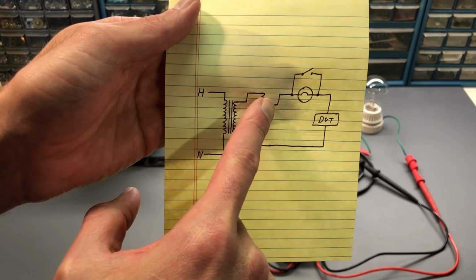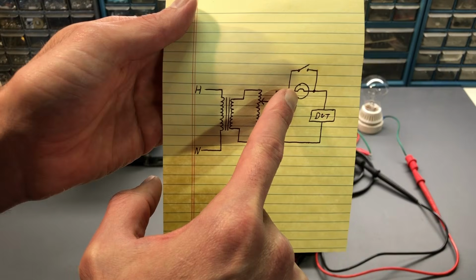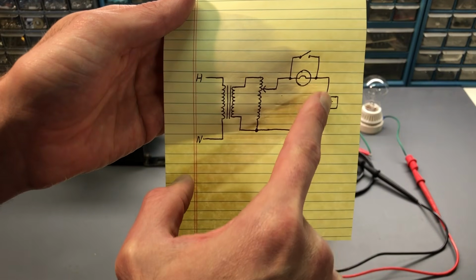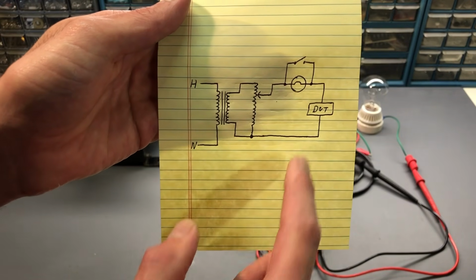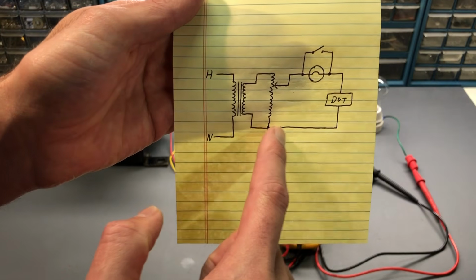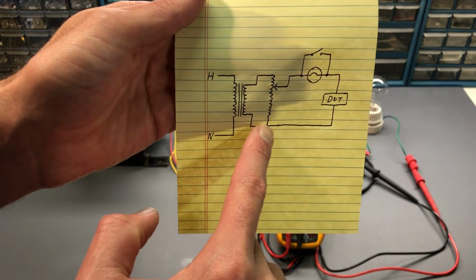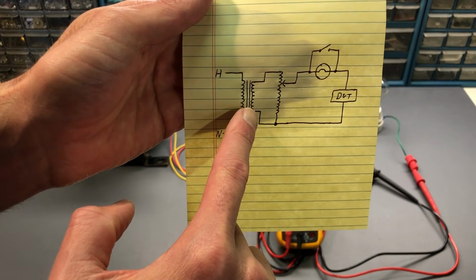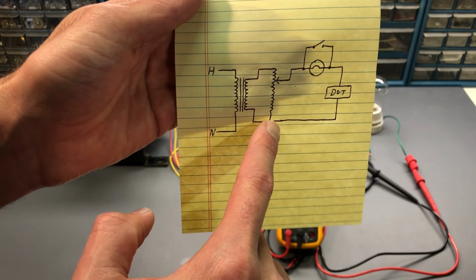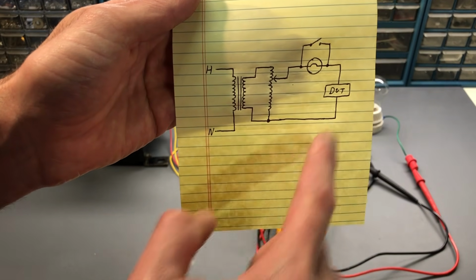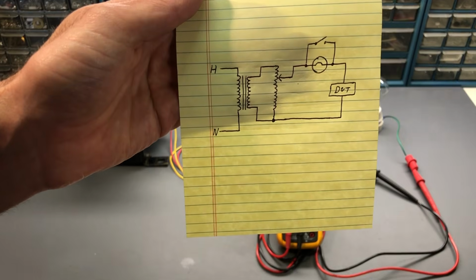is right here. It comes out, it comes over to the incandescent bulb. The other side of that incandescent bulb goes to the device under test, and from the device under test it's returned back to the Variac. This is a common point. You can see the isolation transformer secondary and the other side of the Variac are brought to this common point, as well as the device under test.